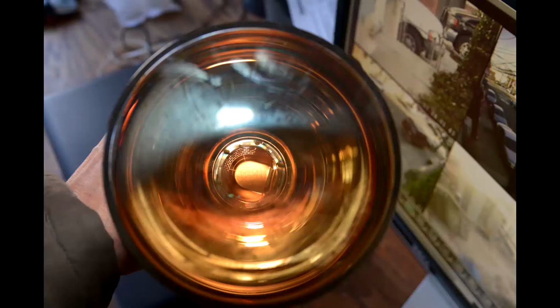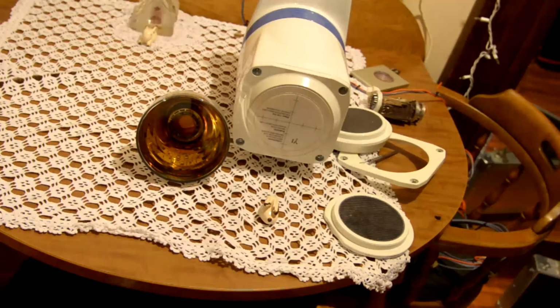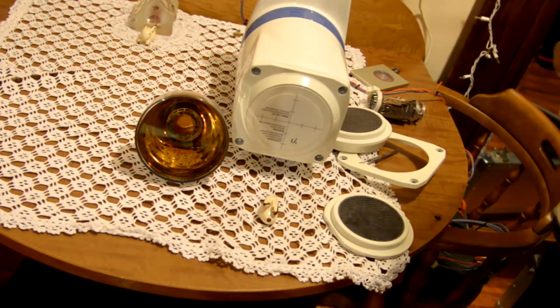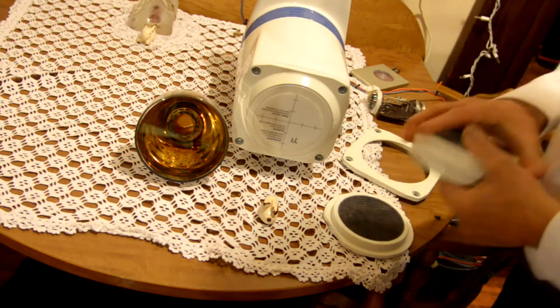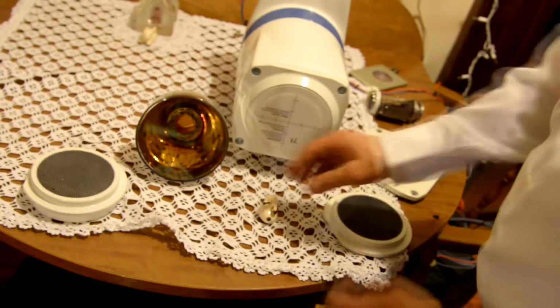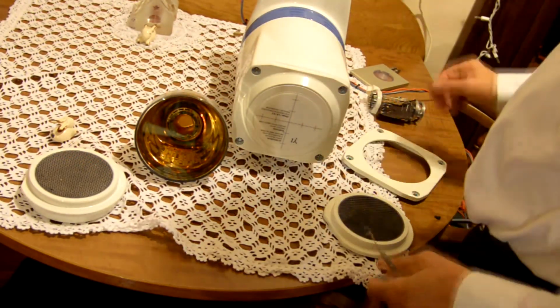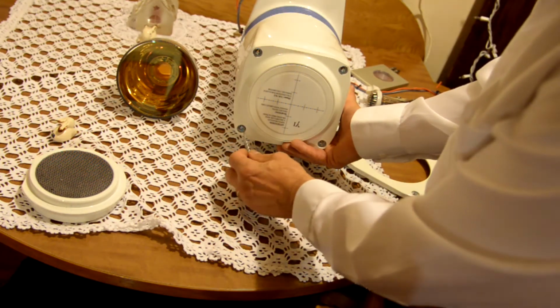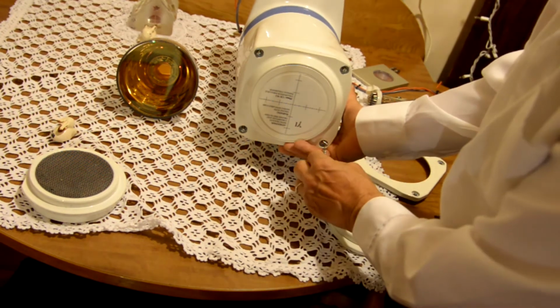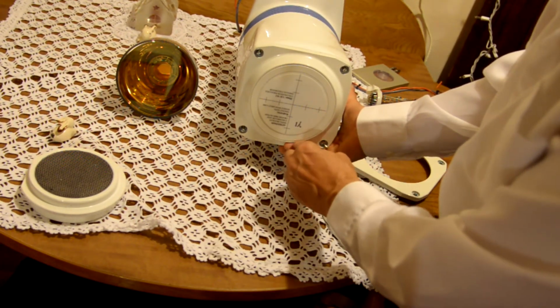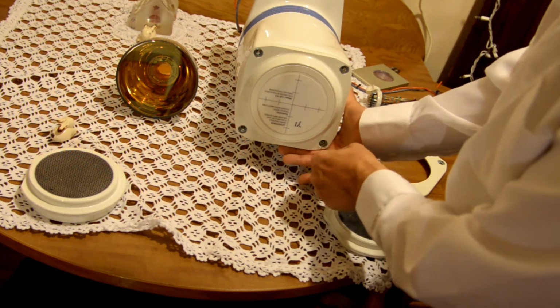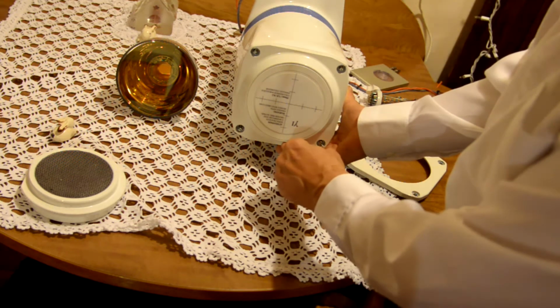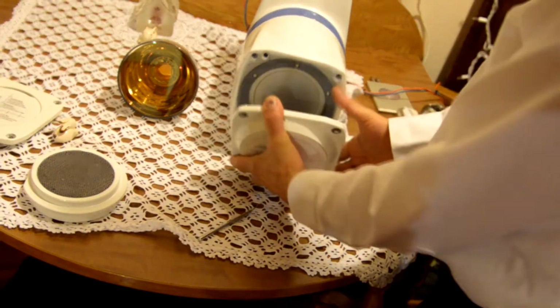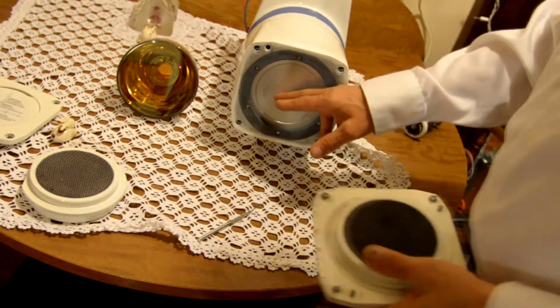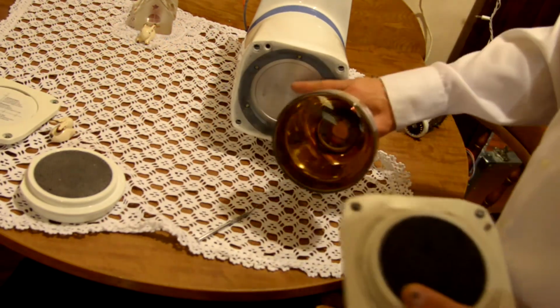A few words about photomultipliers. Photomultipliers are tubes that have a number of electrodes: one anode, one cathode, and dynodes, which are in between. And this particular device is another gamma imager. This one is made not to give a graph, but to give you a physical image like from a camera. It does have a disk in front of it, and that disk is a collimator. A collimator is actually a honeycomb about half an inch thick or less, with dozens of parallel holes in it, and when the gamma ray gets into it, it will make the rays parallel and direct them to the crystal.